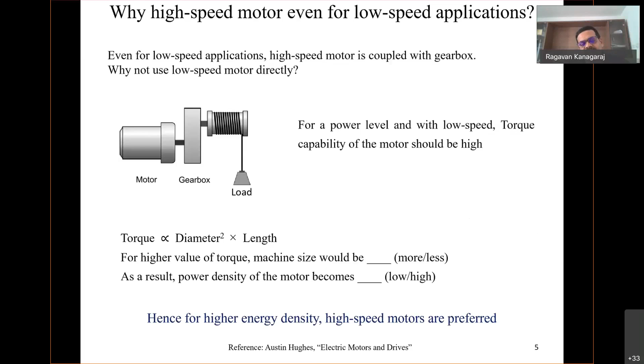Hence, for improving power density or energy density, you prefer a high speed motor. Now come back to this generation: the turbine we have is not directly connected to the shaft of the generator, and the generator is high speed. If the generator goes for the same speed as the turbine, 20, 50, or 100 RPM range, then it's a low speed generator and it will be very big. So to cut down the cost, you have to introduce one more system.